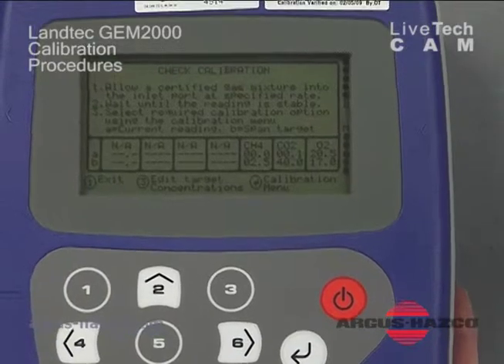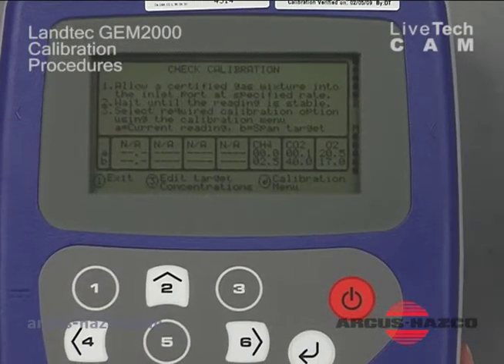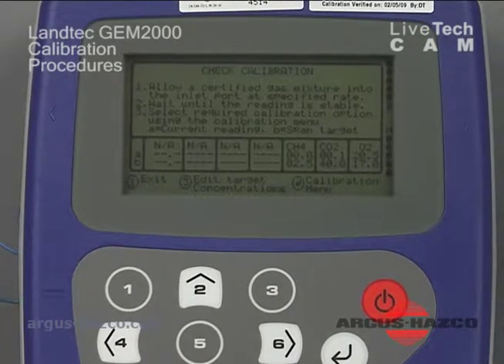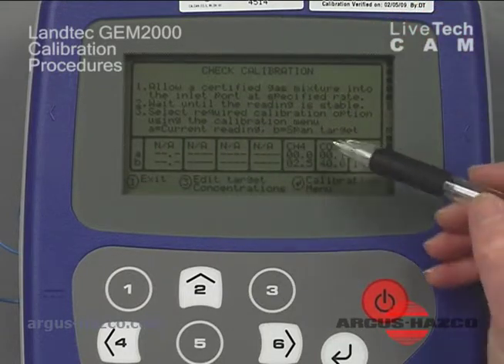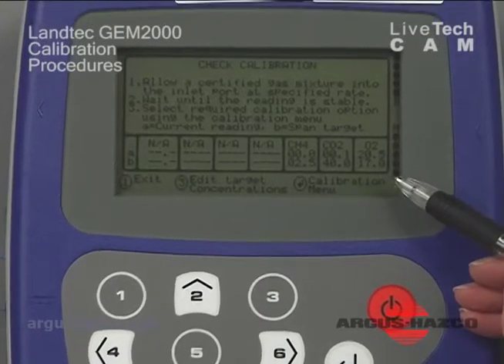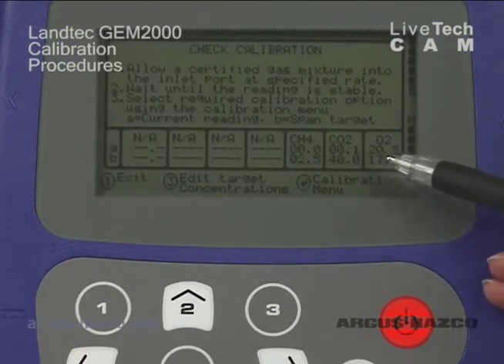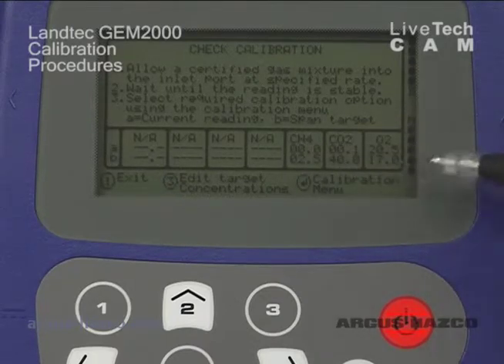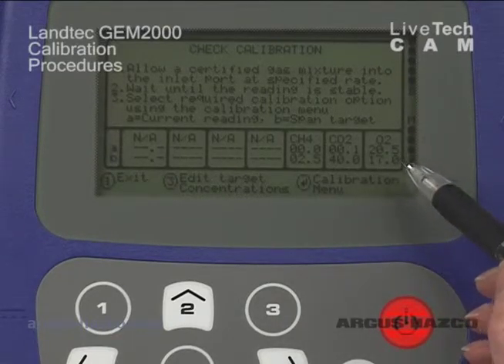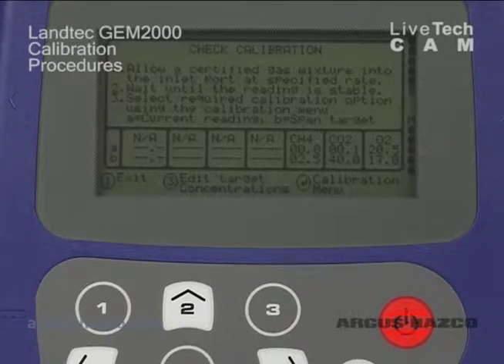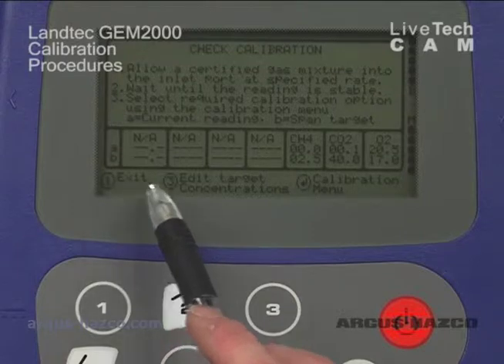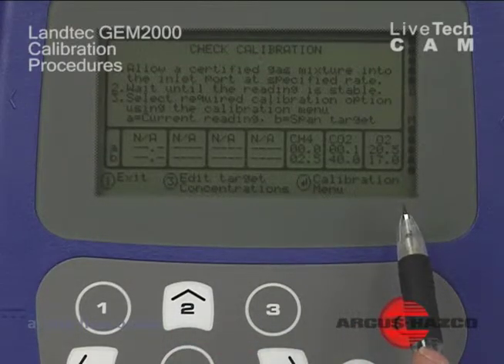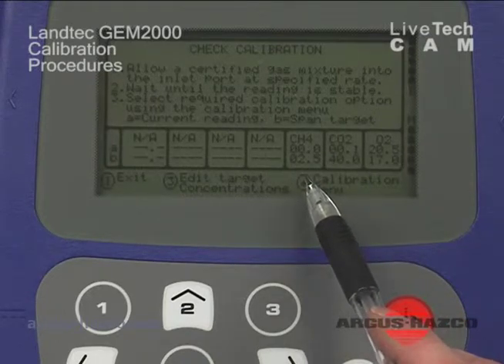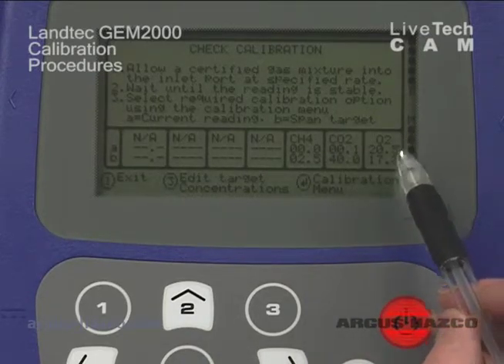And then you will get a check calibration screen with some instructions here. And as you notice right now, we have our dash lines, and then we have CH4, CO2, and O2. The top line, or the first set of numbers, would be our 0 settings, and for our oxygen 0 setting, you would want to have 100% pure nitrogen to zero out the oxygen. And then our second line across here would be our span concentrations. Right now our CH4 is set at 2.5%, CO2 at 40%, and then oxygen at 17%.